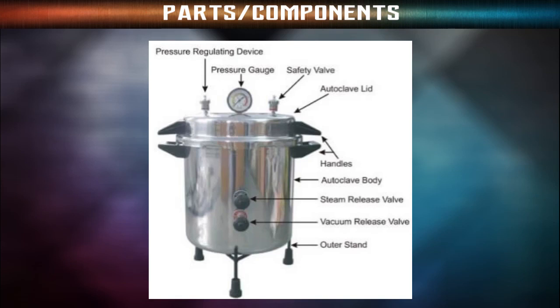Next is the safety valve. A safety valve is present on the lid of the autoclave, which is crucial in cases where the autoclave fails to perform its action or the pressure inside increases uncontrollably. The valve has a thin layer of rubber that bursts itself to release the pressure and to avoid the danger of explosion. Next is the steam generator or electrical heater. An electrical steam generator or boiler is present underneath the chamber that uses an electric heating system to heat the water and generate steam in the inner and the outer chamber.